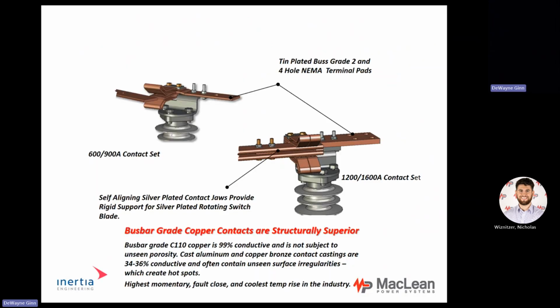Construction of the switches, we use a bus grade copper C110. Actually, it's 99% conductive and not subject to unseen porosity. Porosity is when they pour the copper or even aluminum, and it would have little air holes or bubbles where it comes up. So porosity is very minute in this.